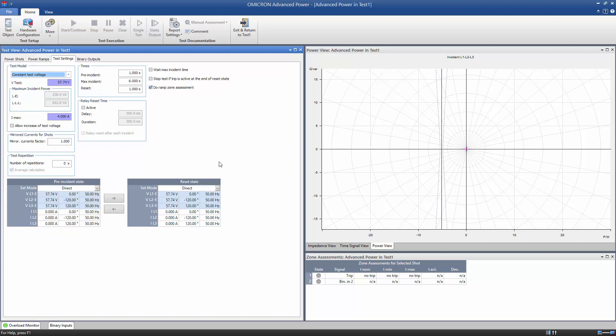It should be set to 0 if you do not want any Pre-Incident output. The Max Incident time applies to shots only. It defines the maximum output time the test module waits to be sure that no trip or alarm occurs when the zone settings do not allow any.